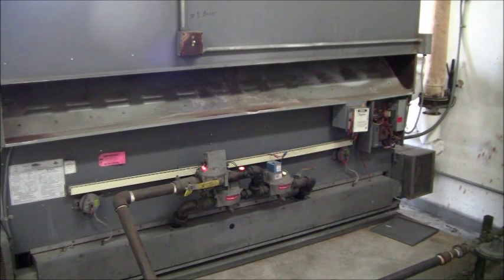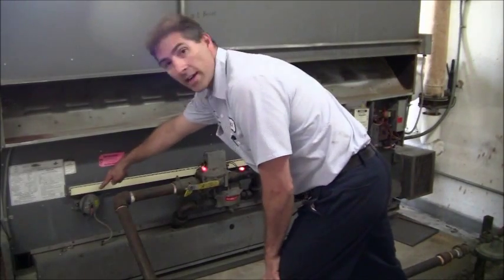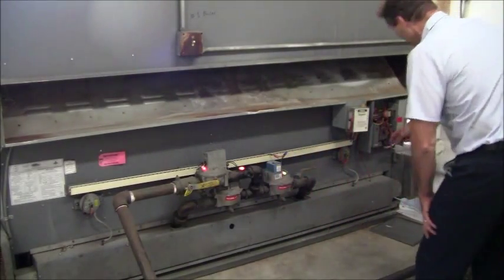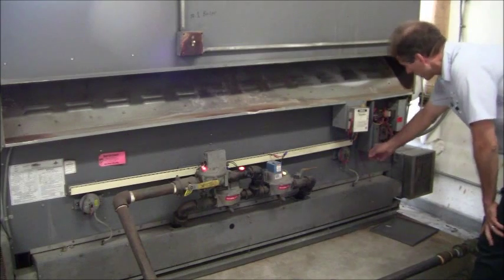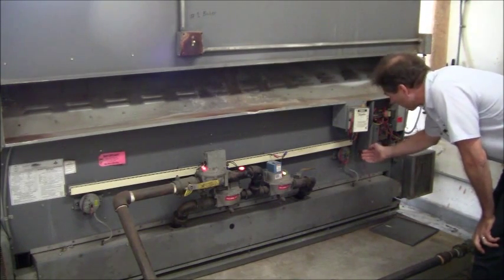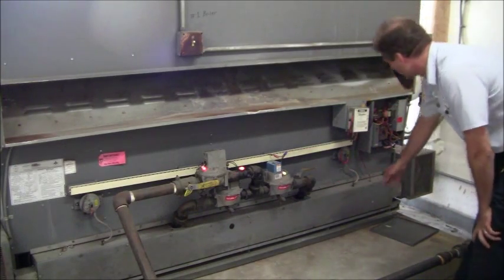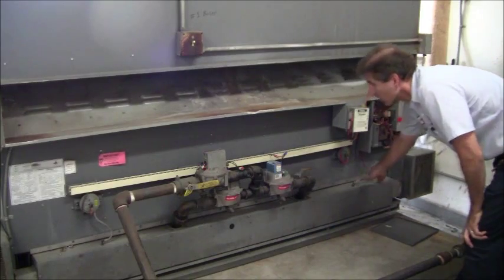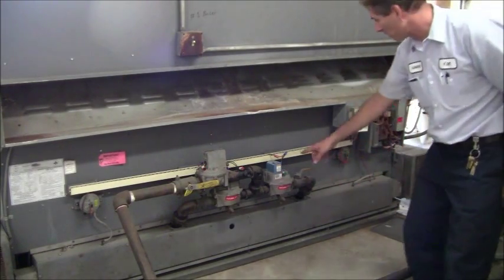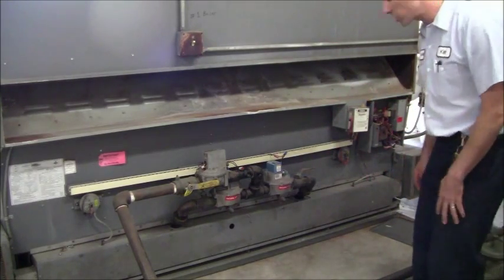The boiler is going through a startup sequence right now. You can see the gas valves are open. There are two air proving switches here — one here and one right here. If I pop this one down, this switch should open and the flame should shut off immediately. I pop that out and you saw the flame shut off, which is what it's supposed to do.